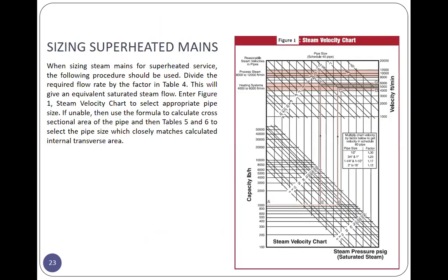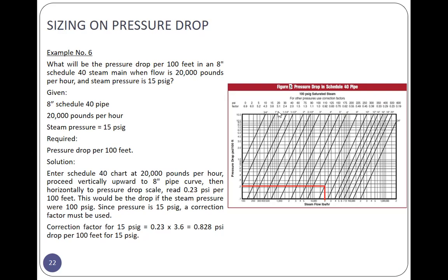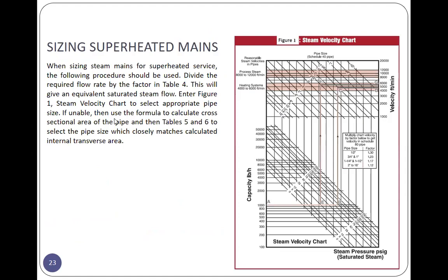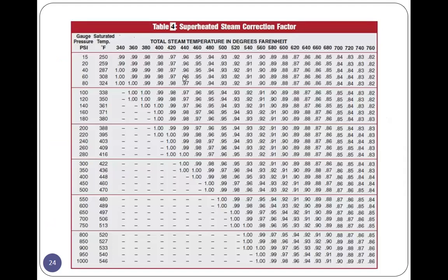So, sizing superheated mains; that was for saturated. When sizing steam mains for superheated service, the following procedure should be used. Divide the required flow rate by a factor in table 4. This is the factor, these are the factors, table 3, table 4. This will give an equivalent saturated steam flow.